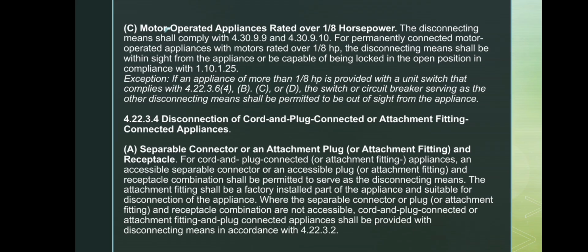An exception is allowed if the appliance has a proper unit switch that meets the requirements in 4.22.3.6 B, C, or D. Then the main switch or breaker used as the disconnect does not need to be within sight. For cord and plug connected appliances, an accessible plug and receptacle or an accessible separable connector can serve as the disconnecting means. If the plug connector is not accessible, then the appliance must have another disconnecting means that follows the same rule for permanently connected appliances.